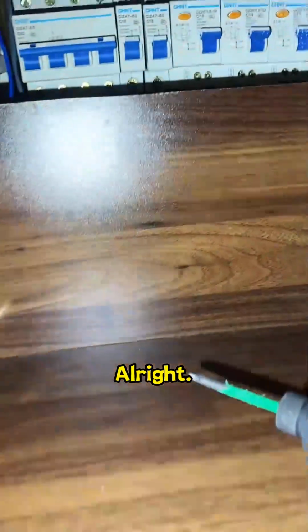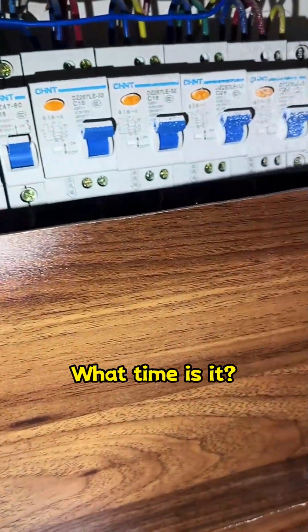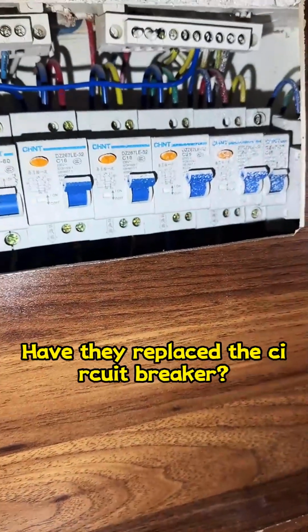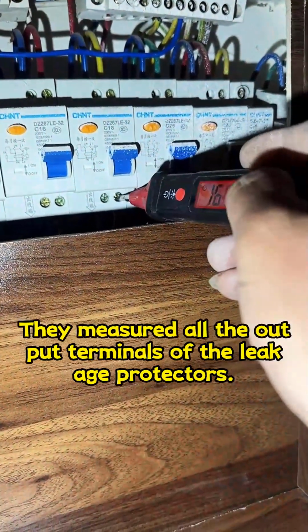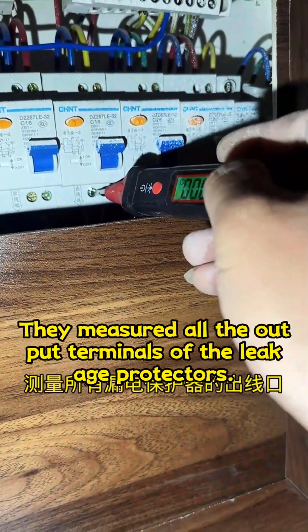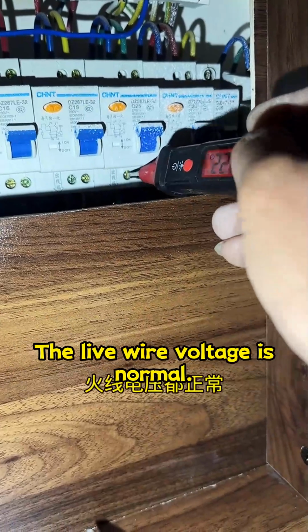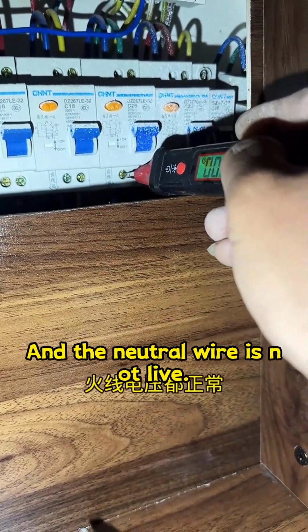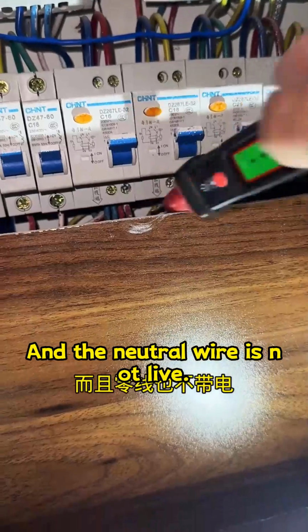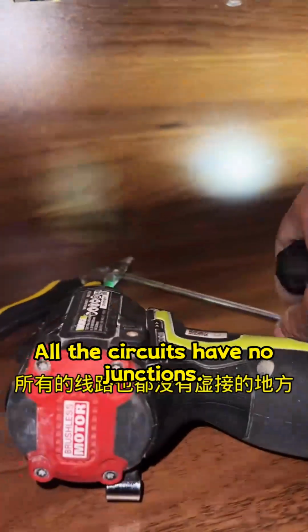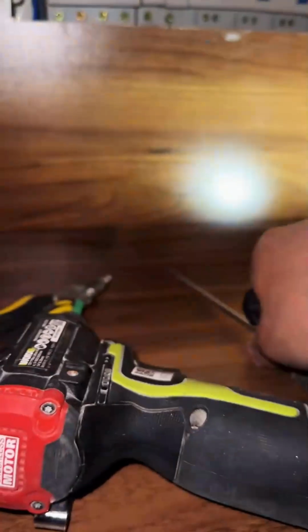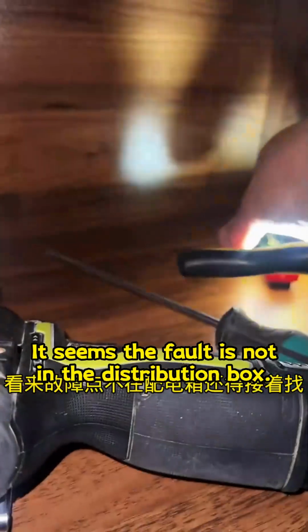Alright. What time is it? Have they replaced the circuit breaker? They measured all the output terminals of the leakage protectors. The live wire voltage is normal, and the neutral wire is not live. All the circuits have no junctions. It seems the fault is not in the distribution box. They need to keep searching.